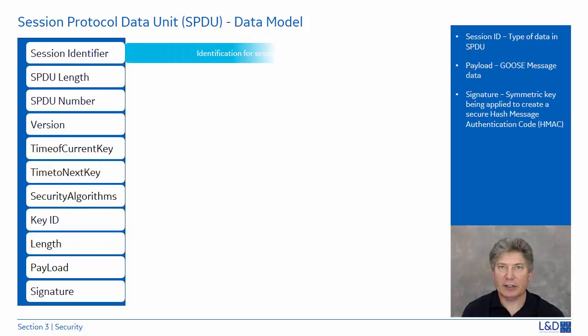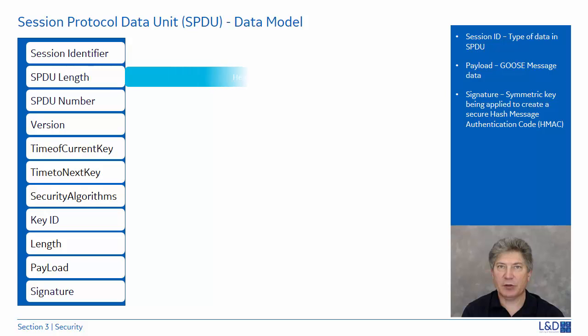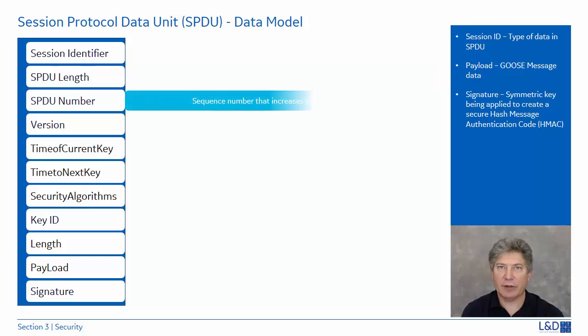The Session identifier indicates what type of payload there is — whether this is a GOOSE or sampled value. The SPDU length is the size of the SPDU, including header content and payload. The SPDU number is a value used to detect duplicates or out-of-order packets. This is maintained by the sender, starts at zero, and increments with each subsequent SPDU.